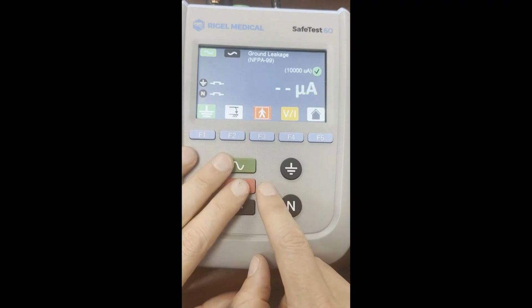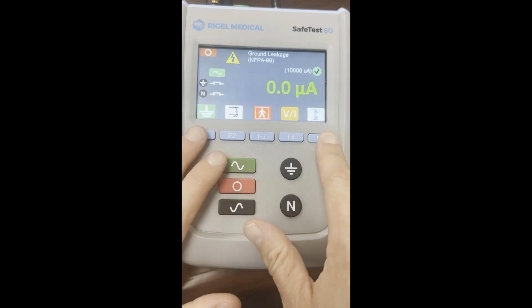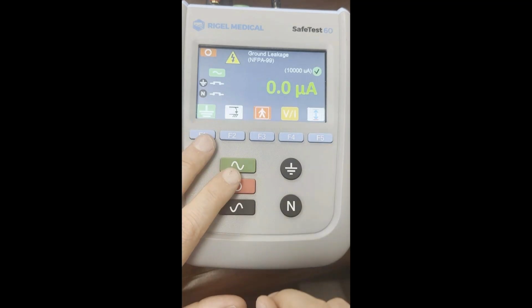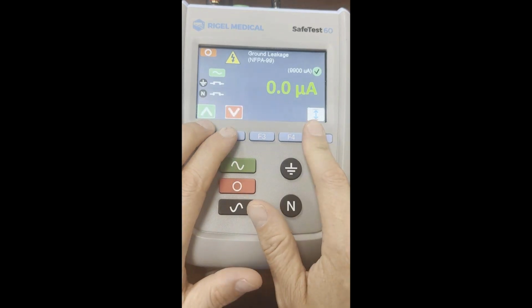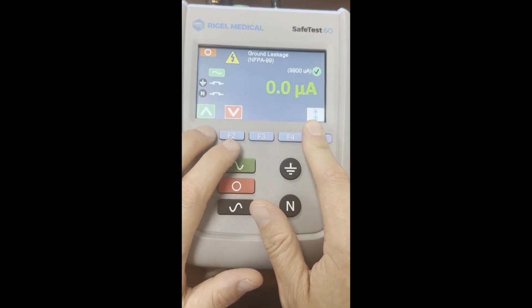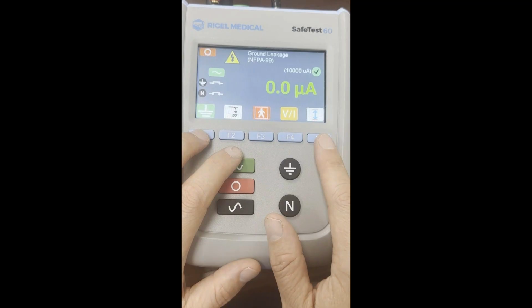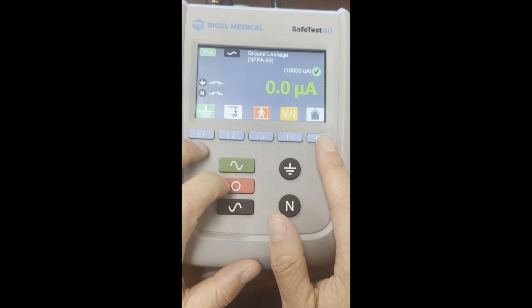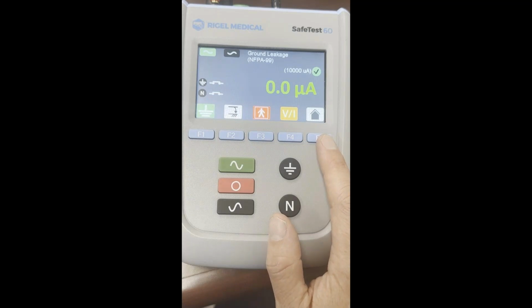Go to ground leakage, hit the active out, and again it's set to the default of NFPA 99. You can change that limit. It's at the max of 10,000 microamps, but you can change that if you've got different limits you need to introduce. But generally it's set to a default, and that's it. Very simple test. Hit the red button to deactivate, and that covers your NFPA 99 tests.